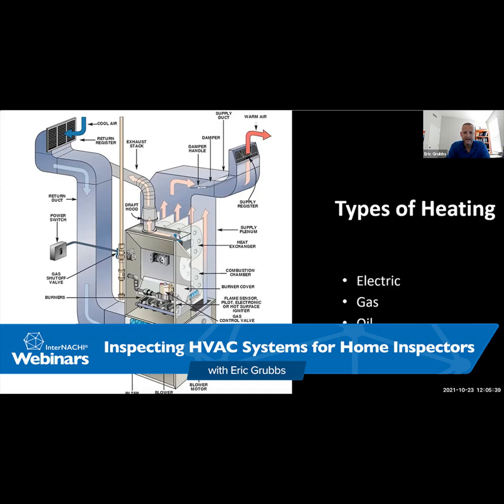And a couple of reasons why. One, they are more efficient. 90+% can range anywhere from 90% all the way up to 98%. And I believe some manufacturers actually have some 99% furnaces out there. When we talk about percentages on fuel, that means that for every dollar you spend on fuel, your rate of return off that money is going to be a little bit less. So if it's a 98% furnace, for every dollar you spend, you're losing 2 cents out of that flue stack on efficiency. On the 80%ers, for every dollar spent, you're losing 20 cents on energy efficiency.